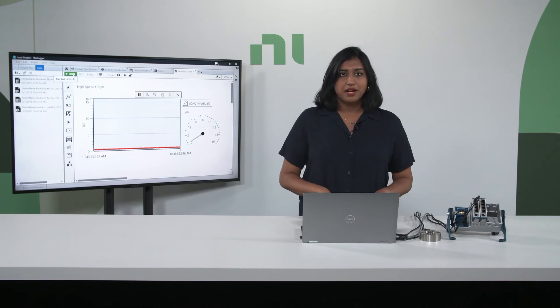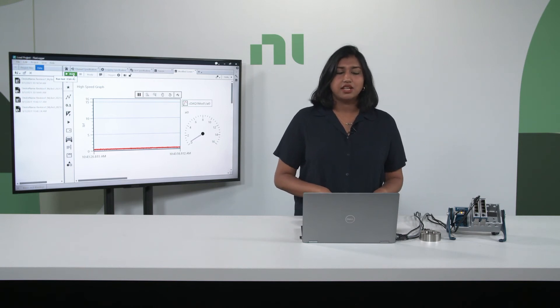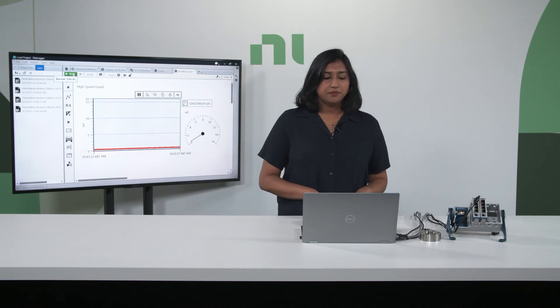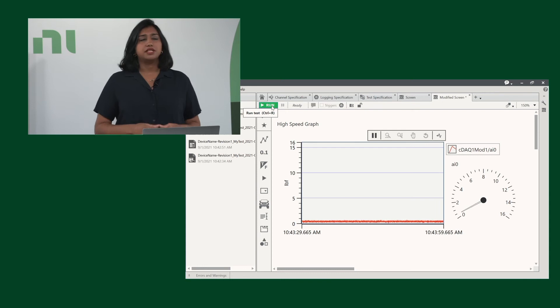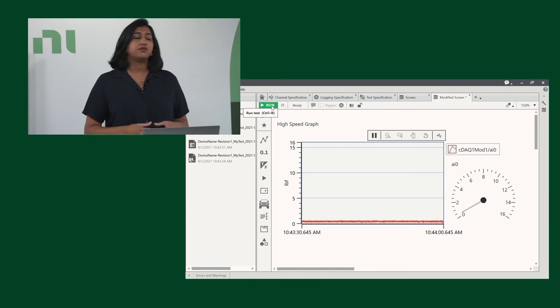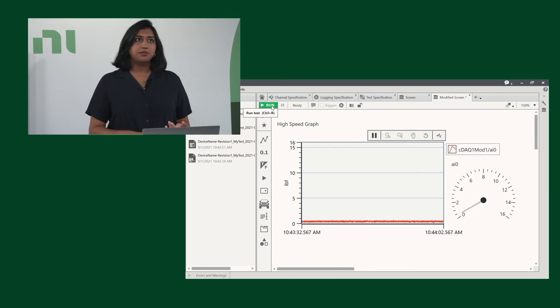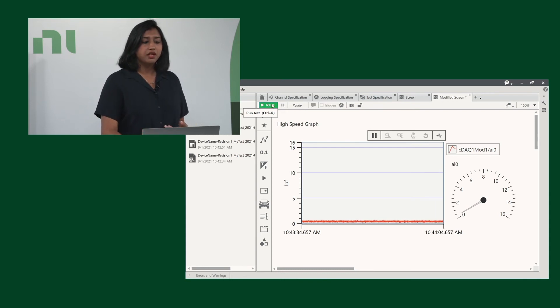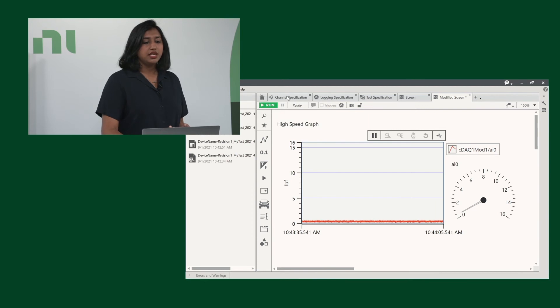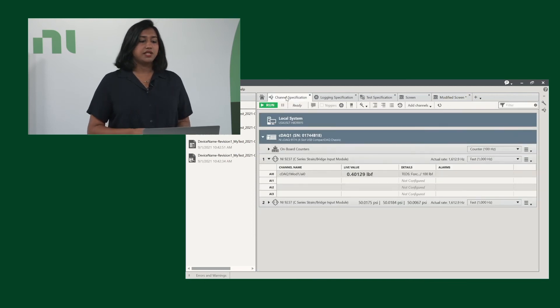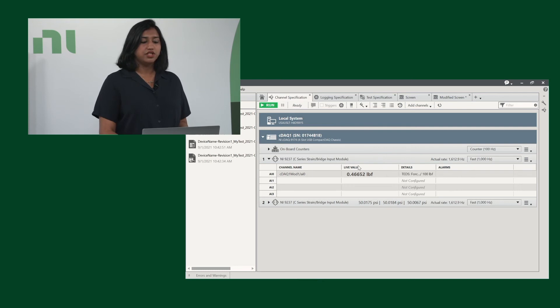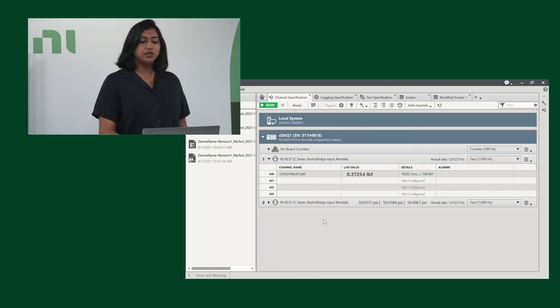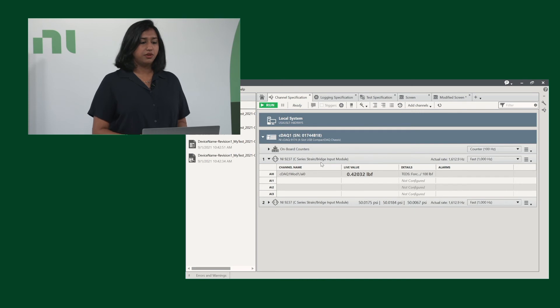Now let's talk about the templates in FlexLogger. NI has designed specific templates for this system. There's a strain template as well as a load template. You will see here in the channel specifications, I've modified it slightly so we can see one of our channels, but it has both the compact DAQ as well as the two modules available.